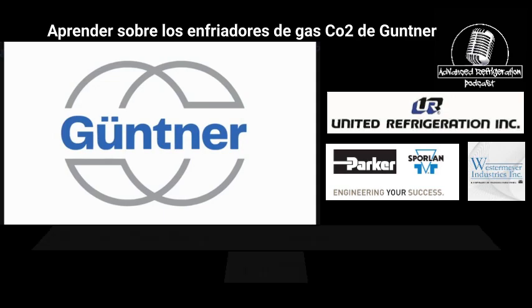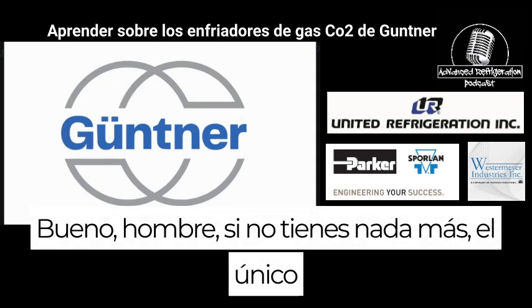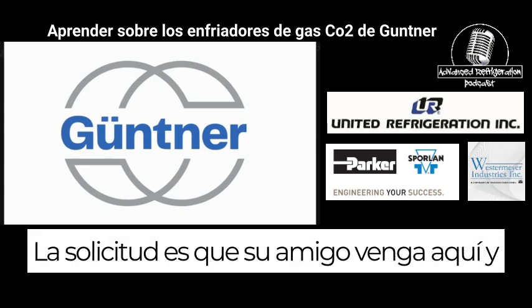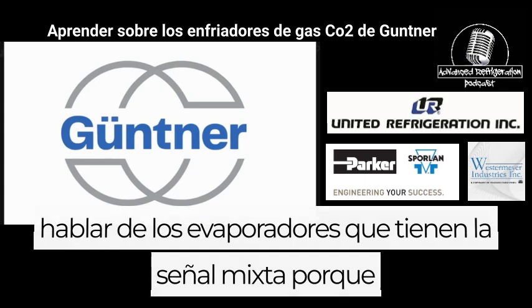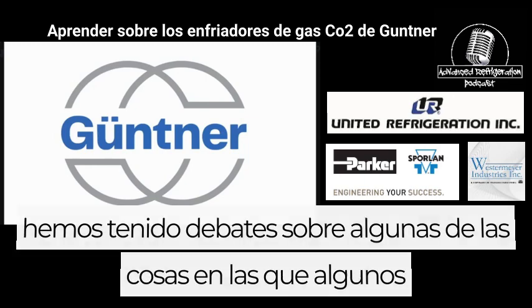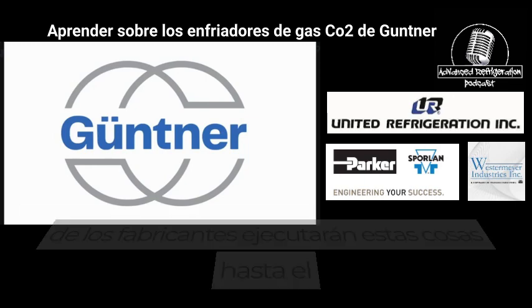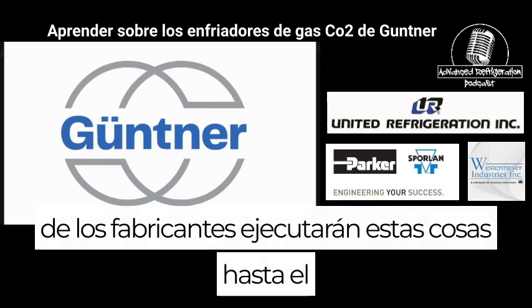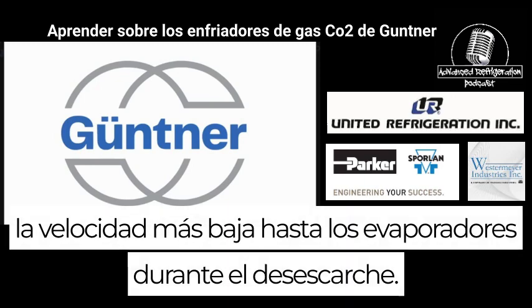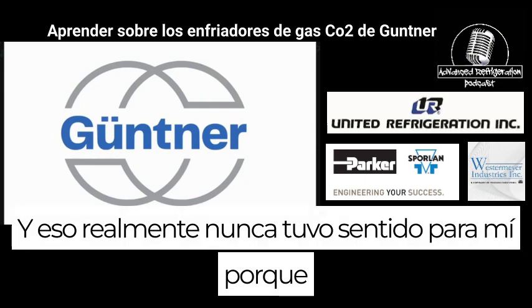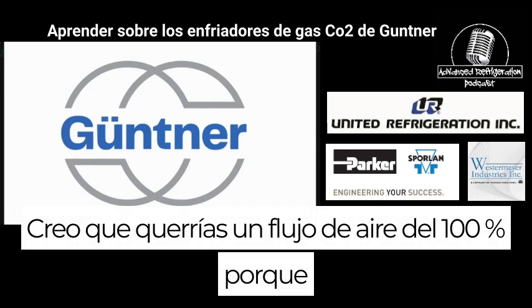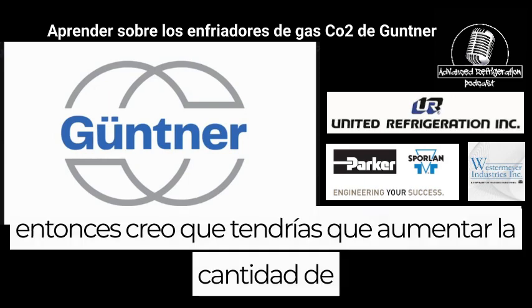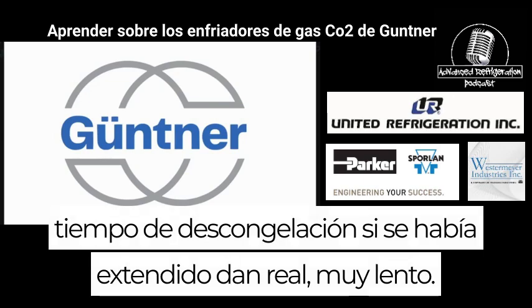Cool. Well, man, if you don't got anything else, the only request that I have is get your buddy to come on here and talk about the evaporators that have the mixed signal, because we've had debates on some of the stuff where some of the manufacturers will run these evaporators down to the slowest speed during defrost. That never really made sense to me, because I thought you would want 100% airflow, since you'd have to increase the defrost time if you ran it real slow.